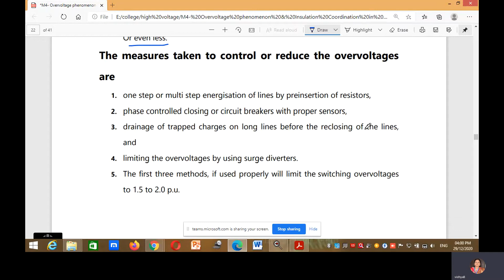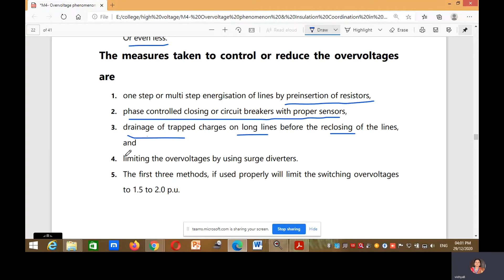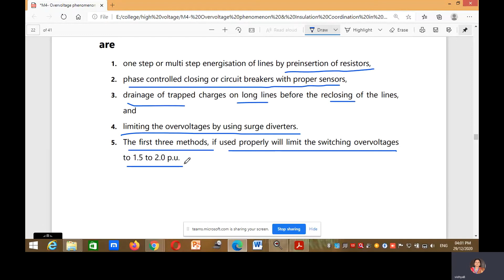Next is phase-controlled closing of circuit breakers with proper sensors. Next is drainage of trapped charges on long lines before the reclosing of the lines. And next is limiting the over voltages by using surge diverters. The first three methods, if used properly, will limit the switching over voltage to 1.5 to 2 pu. Next is the power frequency over voltages in power system.